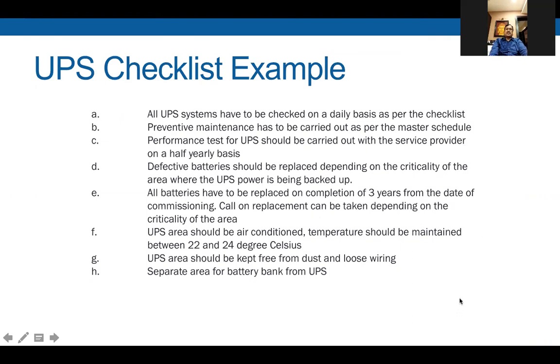So all UPS systems have to be checked on a daily basis. The most important thing is the batteries have to be checked. Batteries now, as per Government of India regulation, have to be separated from the UPS physically. So there has to be a barrier. It must be maintained under air conditioning, that is 22 to 24 degree centigrade, the UPS, and the batteries have to be checked periodically. Actual life is 3 years, but most of our hospitals continue to use that beyond 3 years. But one thing one must notice is the puffing of the batteries. The moment battery starts puffing, that means its life is gone and it can blast anytime if it is used again and again. Next, sir.